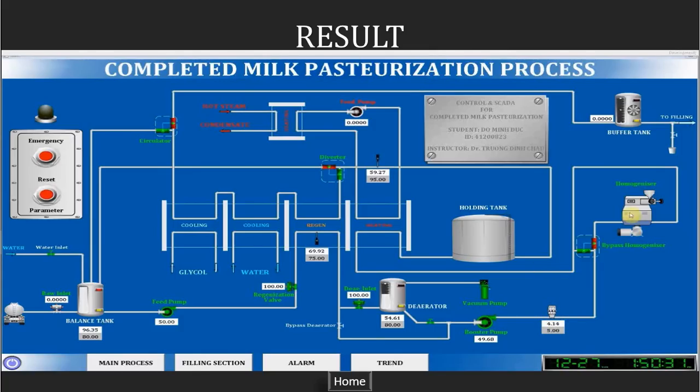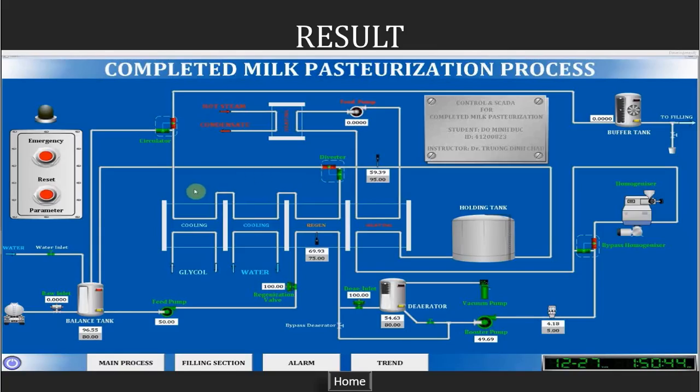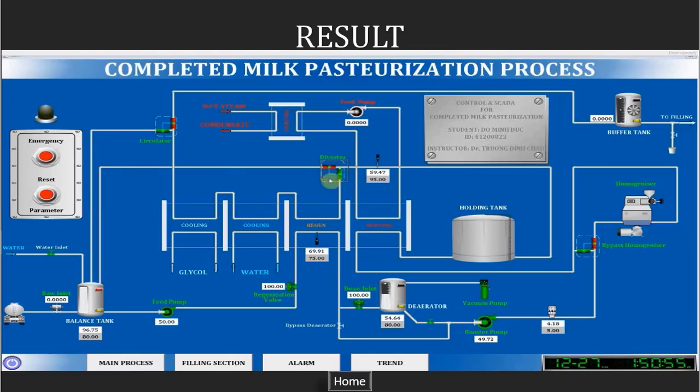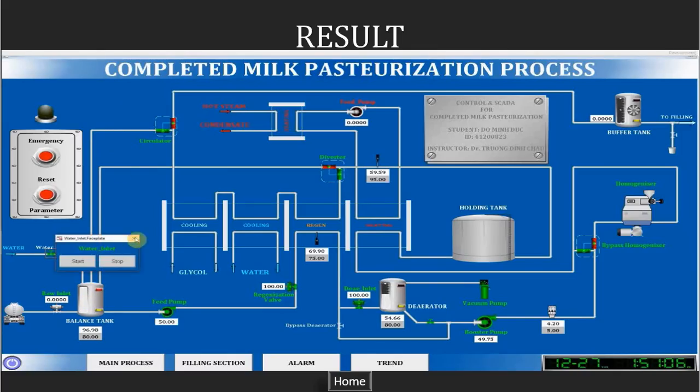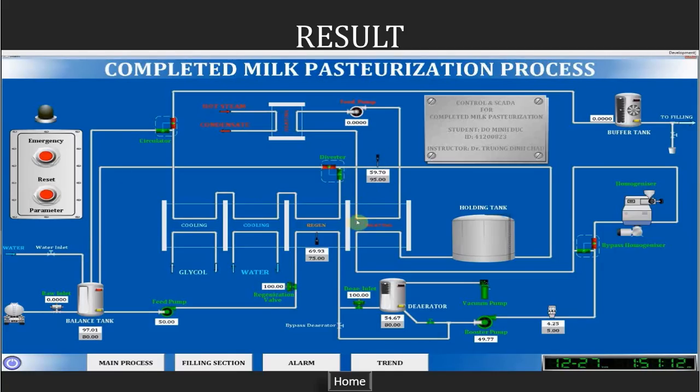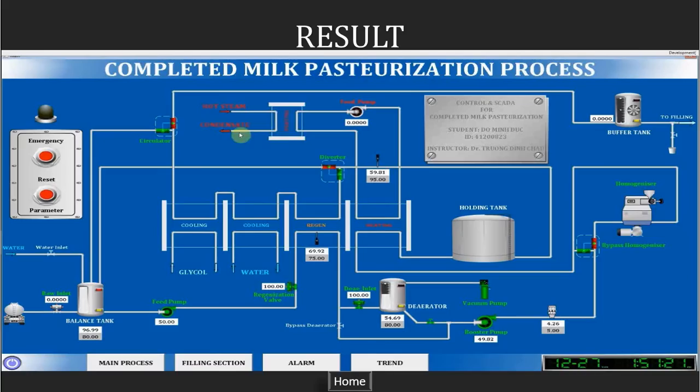In circulation stage, we don't need the homogenizer. So we switch this valve to this position to bypass the homogenizer. The diverter will divert the product back to the balance tank till the temperature is greater than 90 Celsius degrees. But in circulation, we don't need to switch to the diverter position because we already have the circulator. It will drive the milk back to the balance tank. To supply the heat source for the heating section, we have this heat exchanger. On this side we supply the hot steam, and on this side we will circulate water.